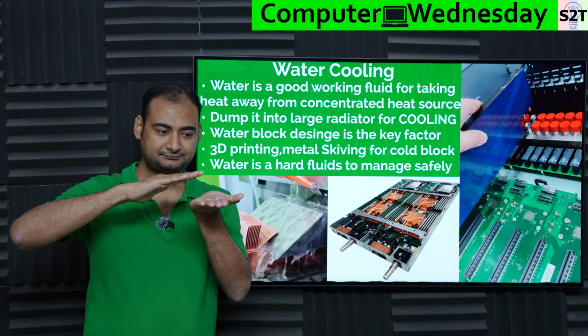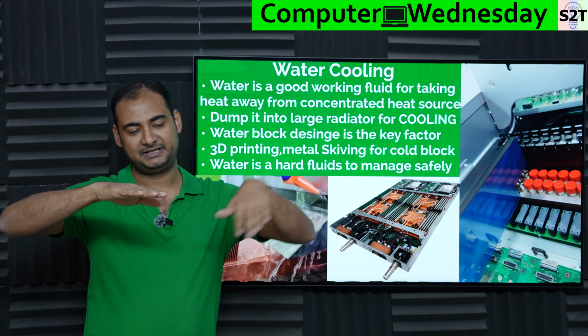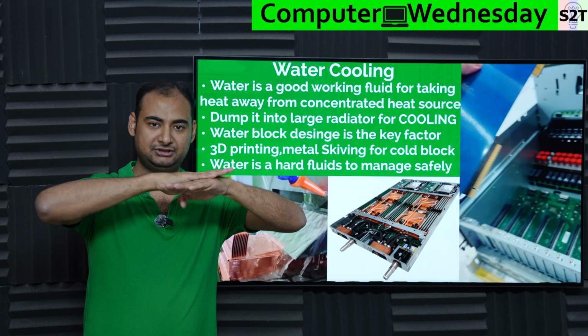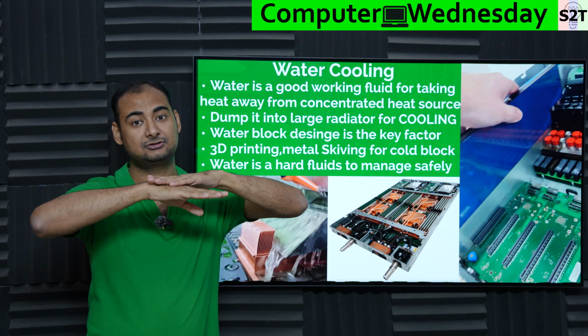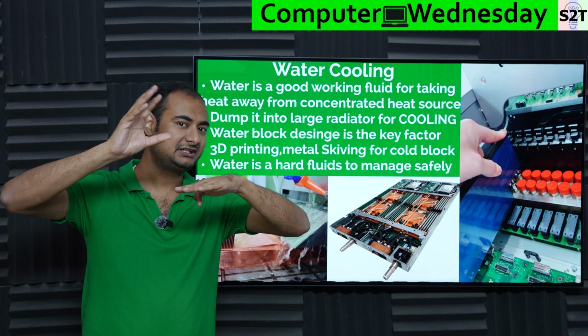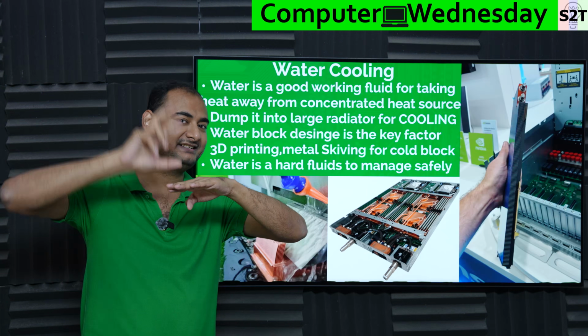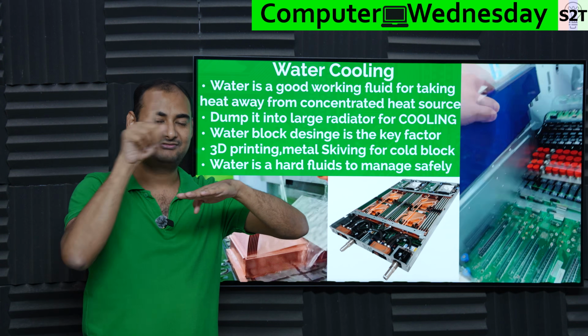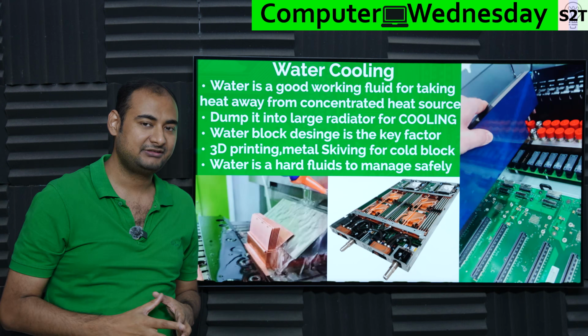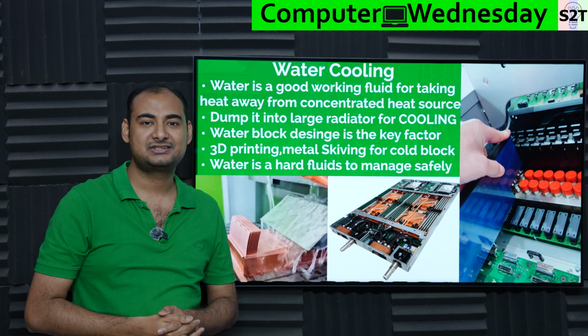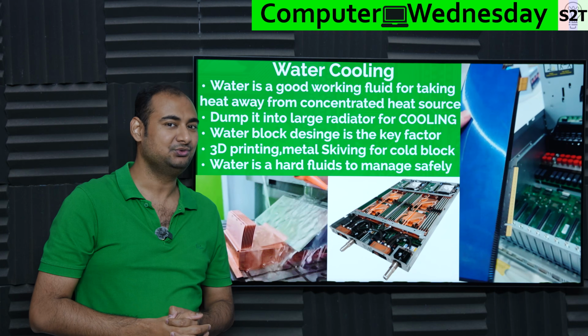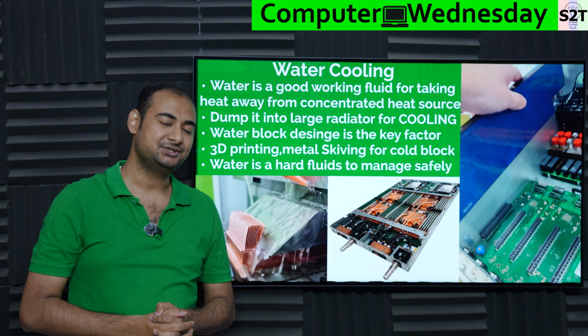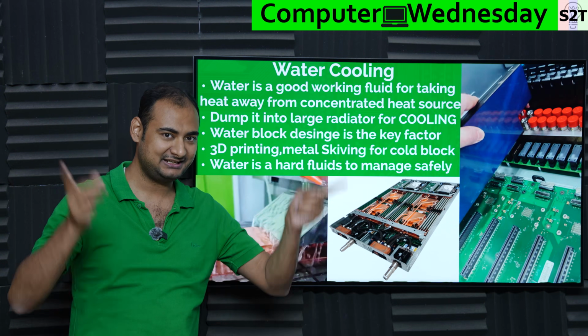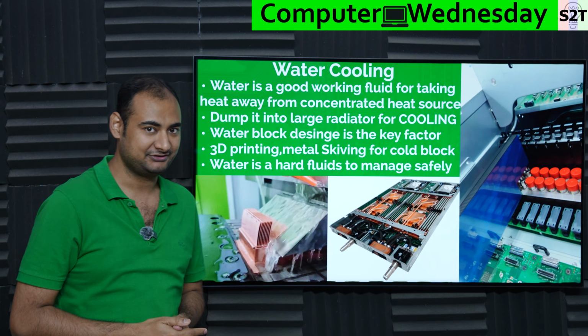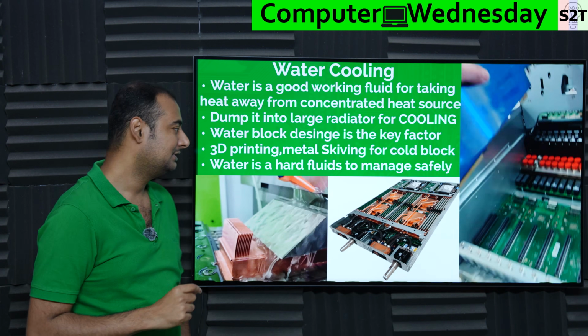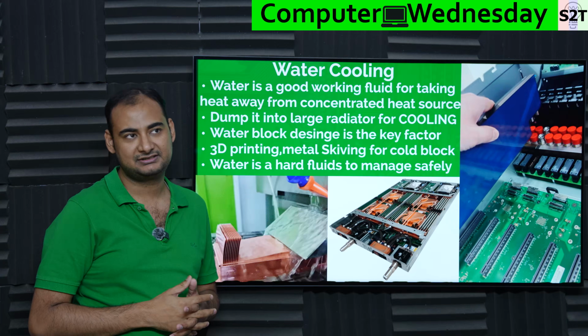You have a silicon die, thermal paste, heat spreader, then thermal paste again, then the cold plate. Now cold plate to liquid, that's the transition phase, a noisy transition. You have solid and liquid, so you have turbulence. Is the turbulence working in your favor or against you? If it's against you, you won't get much cooling, but if it's working for you, you'll get awesome cooling. Water temperature is the same, but your CPU would be hotter if it's not efficient, so that resistance has to go down. Skiving was one of the very successful attempts, and at low cost, this is still the king.